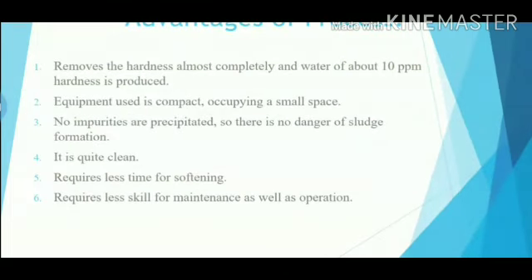Now, advantages of this process. Through this process, the hardness is removed completely and water of about 10 ppm hardness is produced. Equipment used is compact, occupying a small space. No impurities are precipitated, so there is no danger of sludge formation. It is quite clean and requires less time for softening. It requires less skill for maintenance as well as operation.